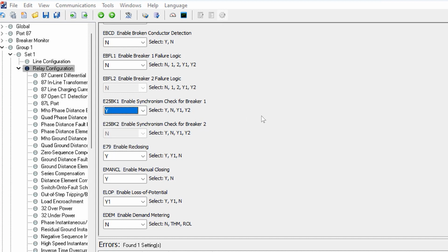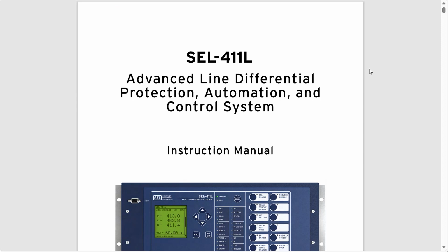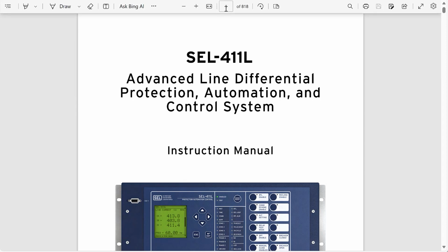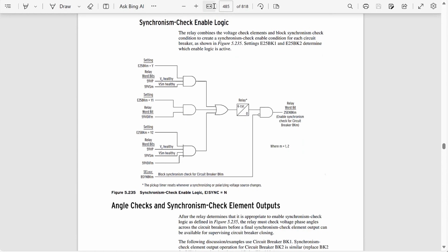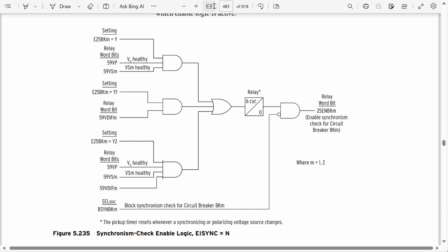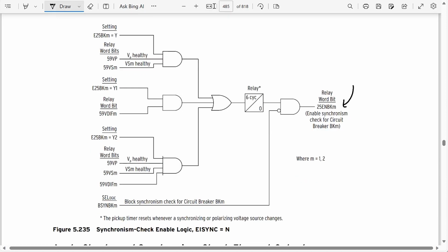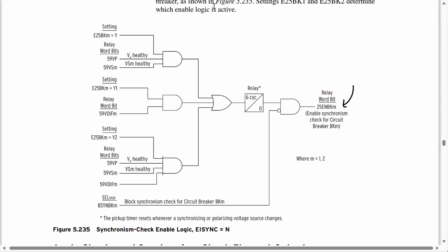So let's enable this element, but let's also go to the instruction manual to see what Y1 and Y2 stand for and what's the difference between setting this element to Y, so yes, or yes1 or yes2. So let's go to the instruction manual, and here I have the instruction manual for the SEL-411L, and if we go to page 485, we're going to see the logic for enabling the sync check element. So this is the internal enable logic, which is this relay word bit over here, 25ENBKM, and then M stands for 1 or 2, meaning breakers 1 or 2. So this is the enable for the sync check element internally in the relay.